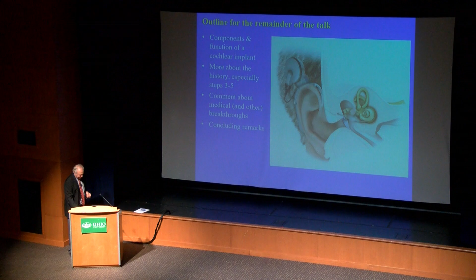That stimulus information is delivered via a cable that leads to an array of implanted electrodes. And here you can see the array inserted into one part of the inner ear and following the helical course of the inner ear. If you look at the inner ear, it looks like a seashell. And the electrode array goes up that helix with a very flexible carrier and a very thin carrier, so it doesn't damage any of the inner ear structures. Each of these electrode sites hopefully stimulates at least a somewhat different population of surviving neurons in the inner ear, and in exciting those neurons, information is transmitted to the brain by the auditory nerve. The component that's not shown in this slide is the user's brain, which might be the most important component of all, as I'll describe in a moment.